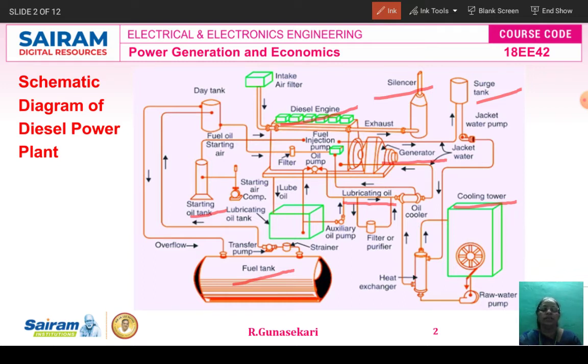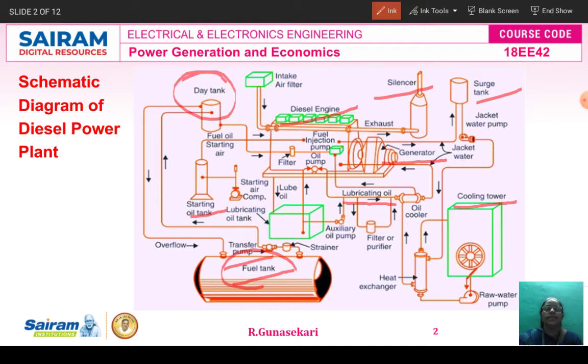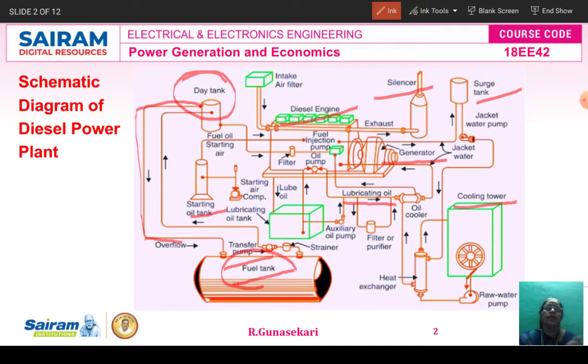What is the basic working operation of the diesel power plant? A huge amount of fuel is stored in the fuel tank. From the fuel tank, through a transfer pump, the diesel is pumped and then goes to the day tank. For example, for a day or week, if over 100 liters of diesel is used as fuel for producing electricity, then 100 liters only is stored in the day tank. If more than 100 liters, the extra diesel comes back to the fuel tank — if overflow, that diesel will again return to the fuel tank.